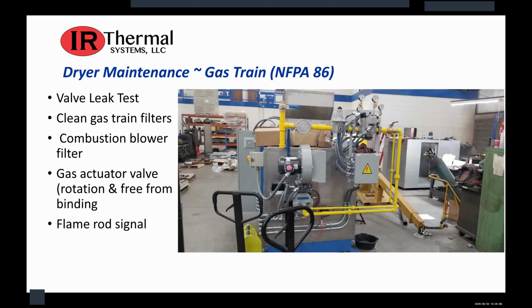One of the areas that you see most overlooked on older systems is the natural gas train. That is what controls the safe delivery of natural gas to an individual burner. And NFPA 86 is a fantastic document that gives you the regulations and recommendations for furnaces and ovens. So if people have a furnace or an oven, having an up-to-date copy of the NFPA 86 manual is really important. Or you should be in contact with a maintenance group that does spend the time to keep up to date with those regulations.